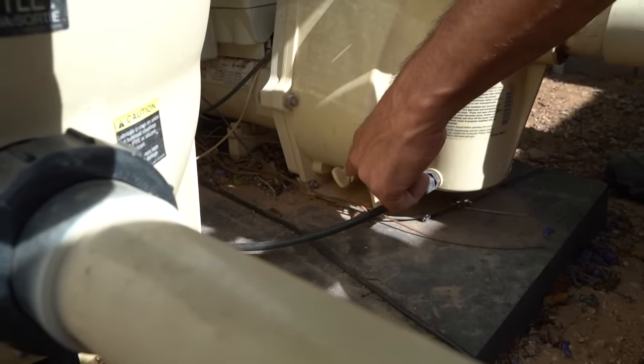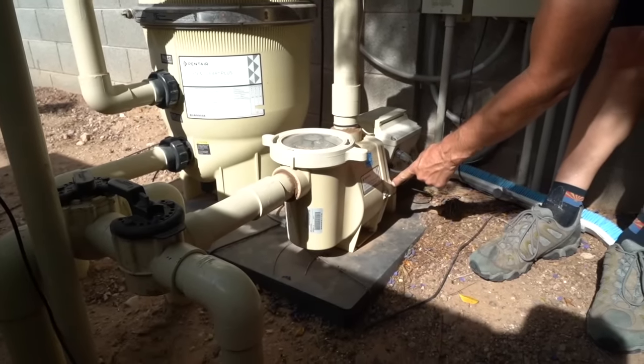Don't forget to check the pump. You've got two plugs on the bottom. You've got your seal plate and the outlet nipple — that's the pipe that comes from the top — and also the main seal. After that, you'll want to shut the system down for the duration of the bucket test.